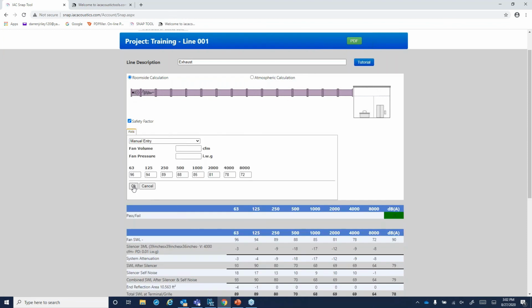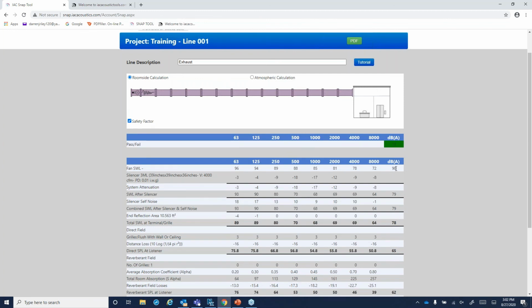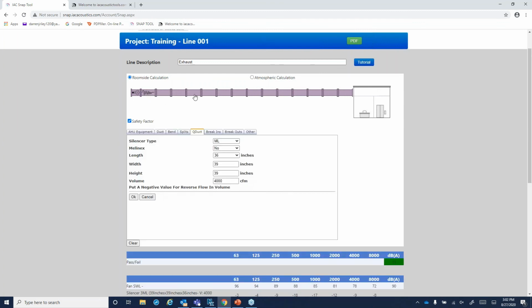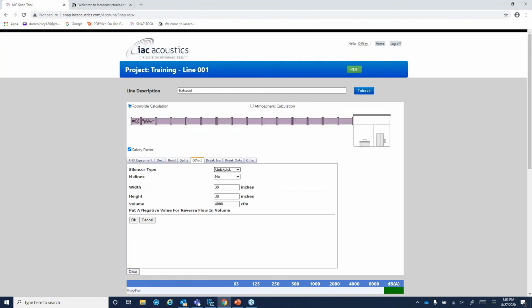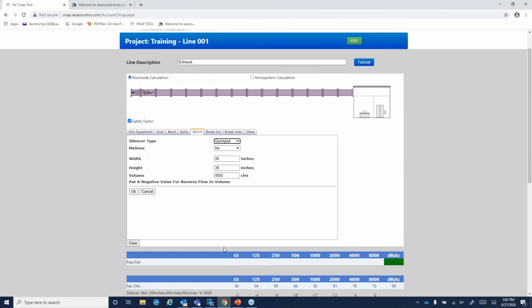So if we look at that and you click OK, we have a starting dBA at 90. We got to get to 81. So what you do then is there are many different segments through here. For this specific example, we are going to be applying a silencer directly to a fan, and it's going to be the exhaust, so it's going to be right up against it. In this area, we know the length, we know the width, we know the CFM. You do not know what type yet. So what I typically always say is quick pick. And it will either give you 1, it could give you 10.